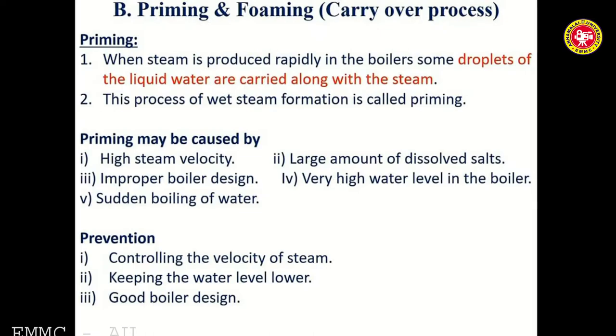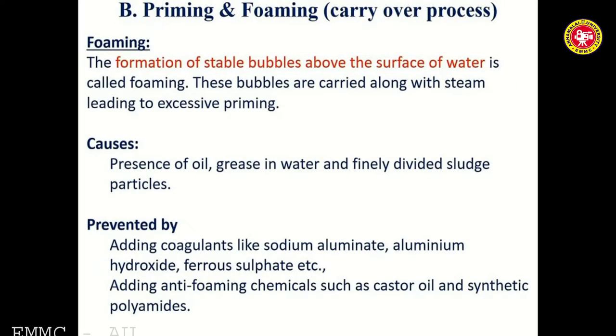The reasons for priming are: high steam velocity, large amount of dissolved salts in the boiler feed water, improper boiler design, very high water level, and sudden boiling of water. Foaming is the formation of stable bubbles above the surface of water; these bubbles are carried along with steam, leading to excessive priming.